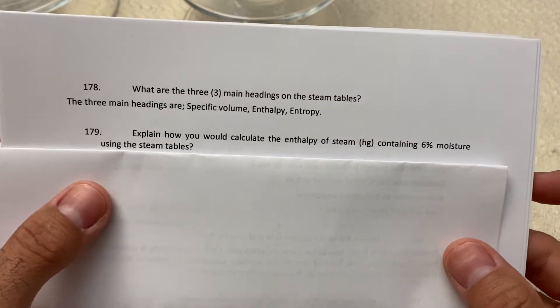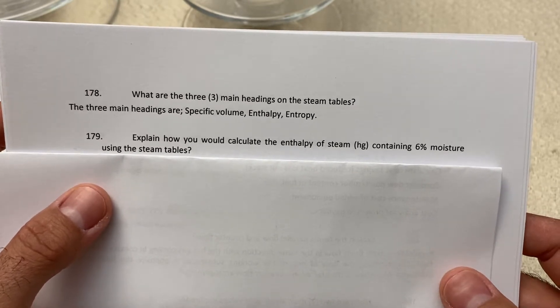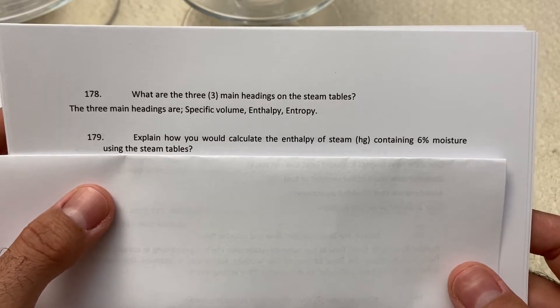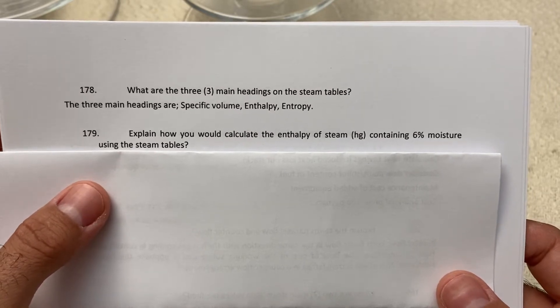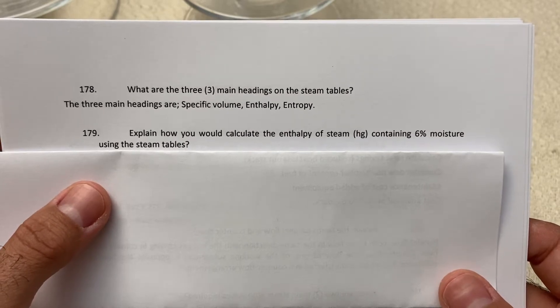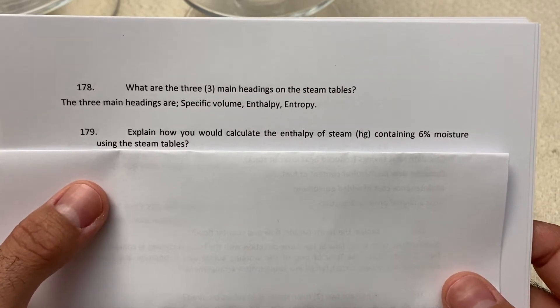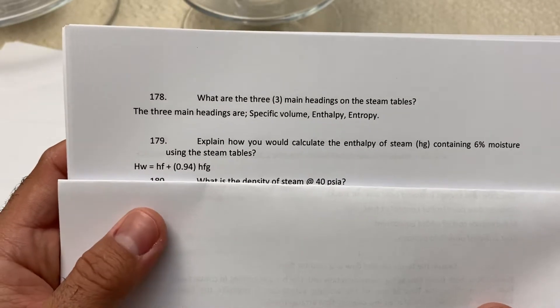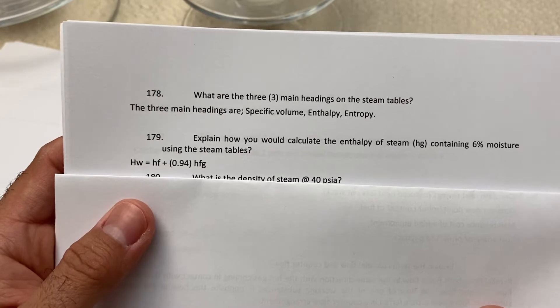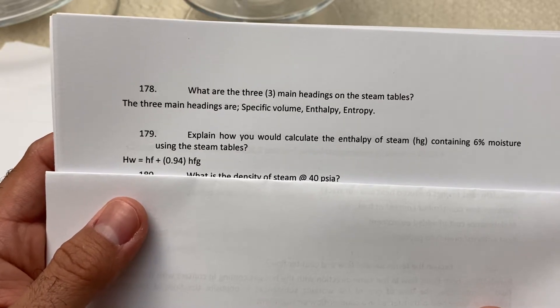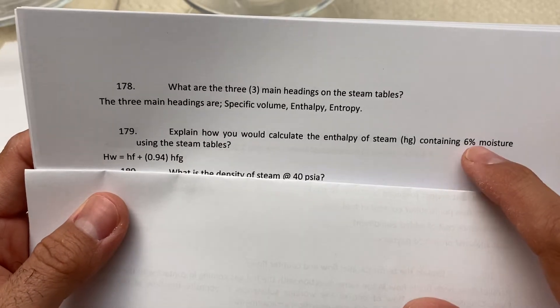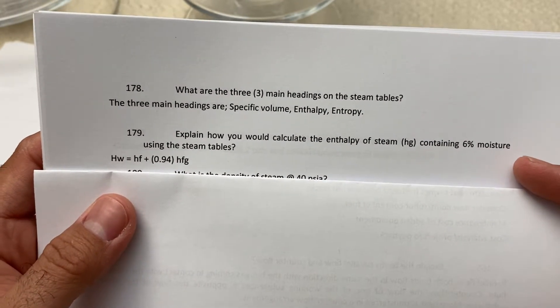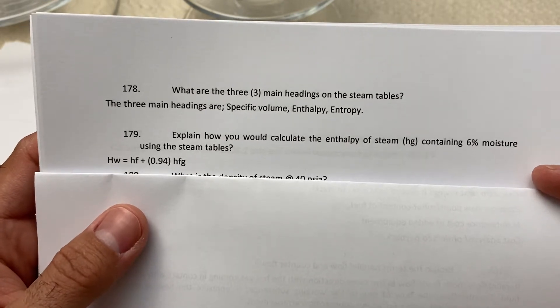Explain how you would calculate the enthalpy of steam containing 6% moisture using the steam tables. The calculation is H equals HF plus x times HFG, where x is 0.94 — because six percent moisture means you subtract 6% from 100%, giving you 0.94. That factor gives you the answer for the six percent moisture condition.